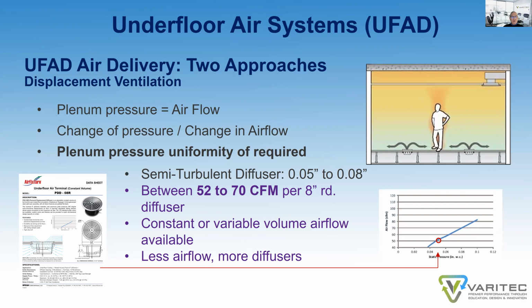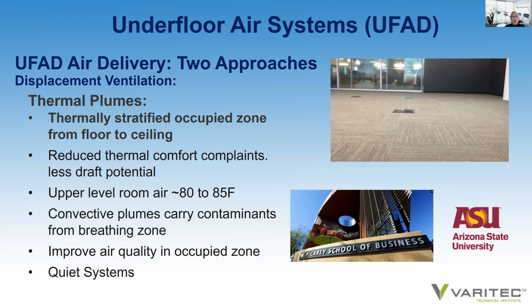And by the way, on the semi-turbulent and the displacement diffuser comparison, I see I have that not properly titled. It says semi-turbulent diffuser. It should say displacement. I apologize for that. Anyway, with these diffusers, you'll need more of them at the lower airflow provided because they're unable to discharge the same volume of air. So there's a cost impact to that. Again, thermal plumes occur with a displacement ventilation UFAD solution, a thermally stratified environment. All the other properties as the semi-turbulent take place.